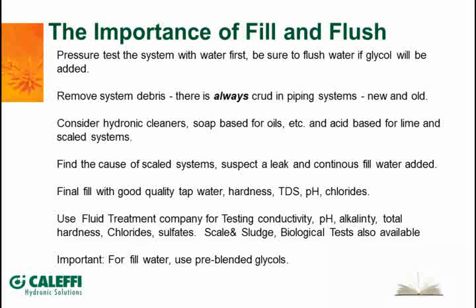And probably on the bigger side of that, we were involved in a job down in Mississippi recently, a big solar job. I think it was like 48 collectors or more. And that system was put together with welded pipe. It was 2-inch welded pipe. It was underground. They had to go out to a ground-mounted array across the parking lot, probably a couple hundred feet away, and it was all welded pipe. So you can imagine when they're cutting that pipe with abrasive saws or chop saws, and then they're welding it and mitering those joints. A lot of that debris is inside there, and you certainly don't want that coming back and getting into your pumps and into your control valves. So a system like that definitely has to be flushed out.